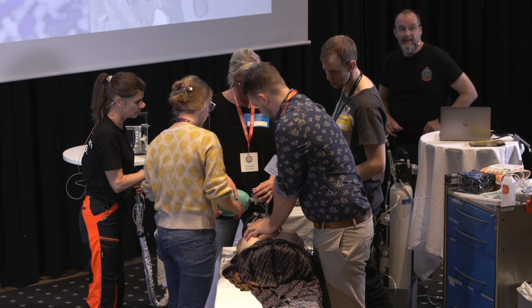Yeah. Okay. Now you do not need to breathe for the patient. How do we operate this to get feed? So that's an adjustable PEEP limiting valve, APL valve. It's on a spring. You screw it down. If it's fully screwed down, the PEEP is 60.